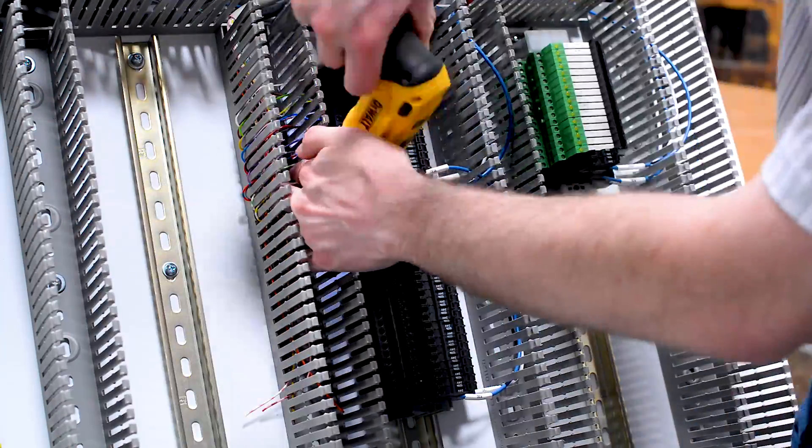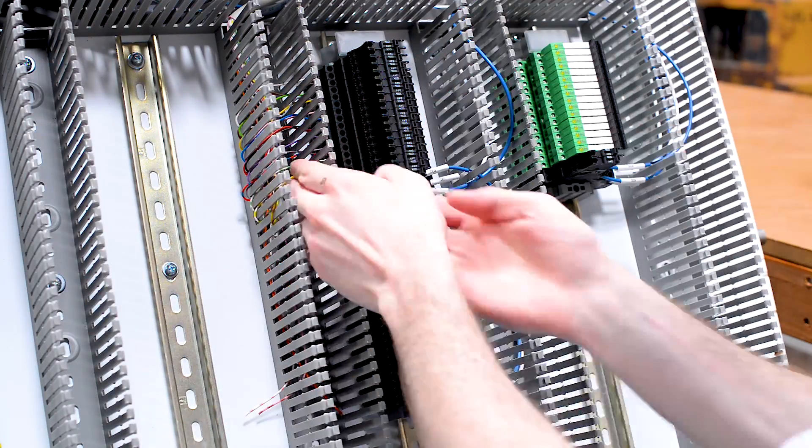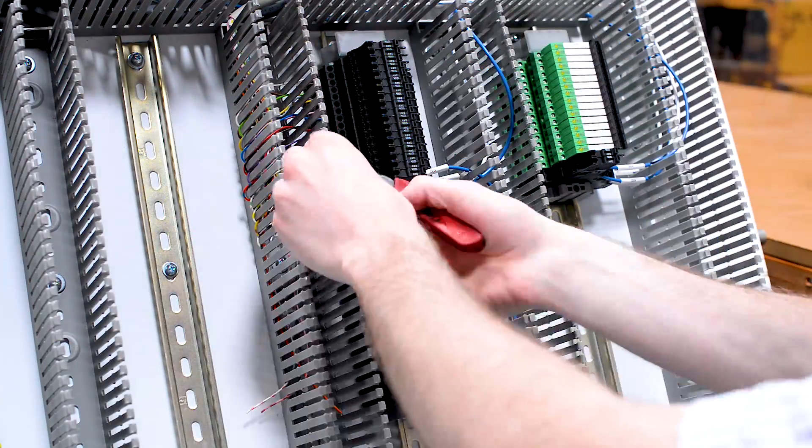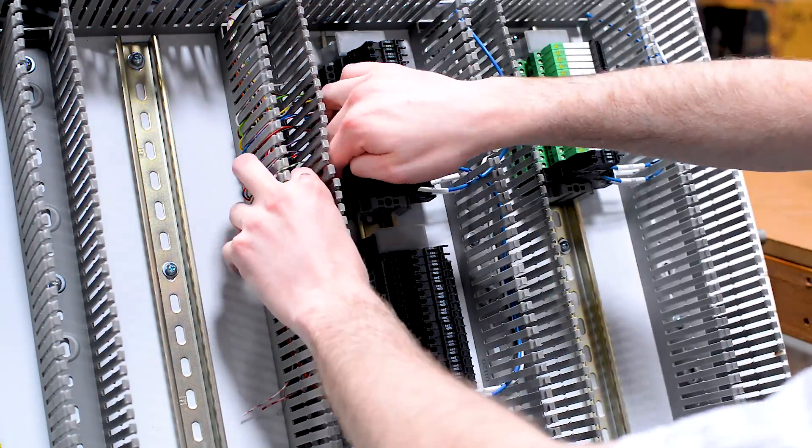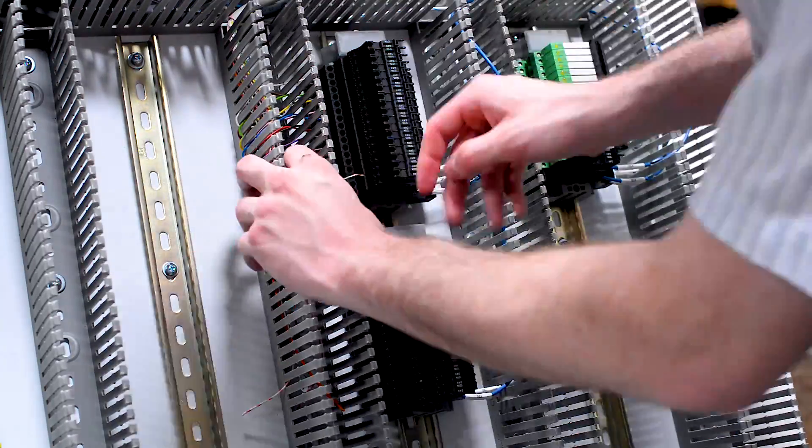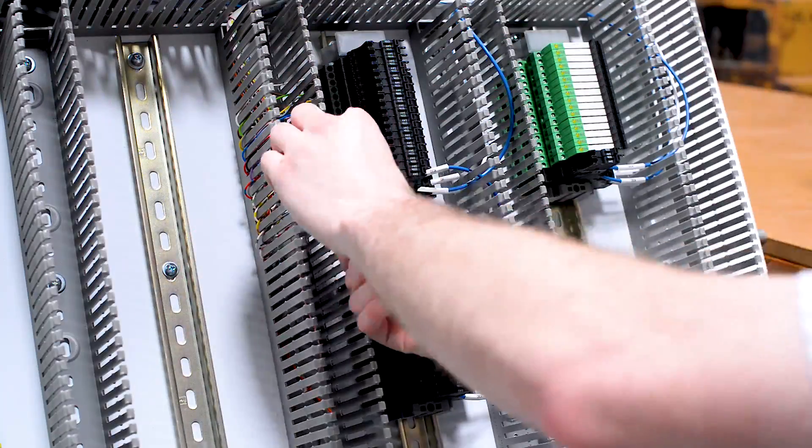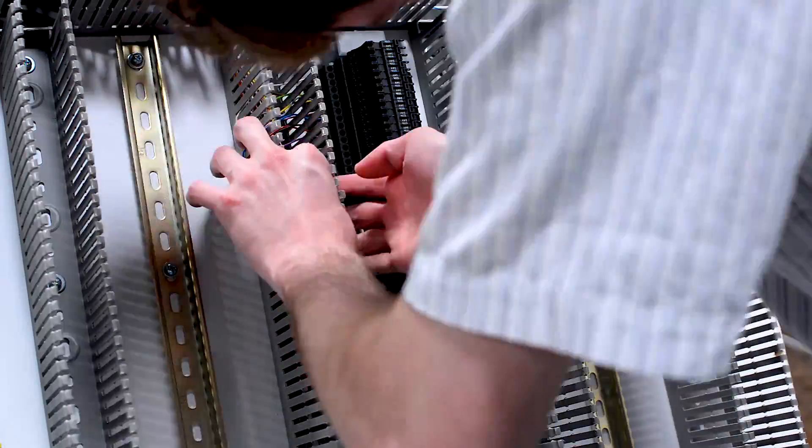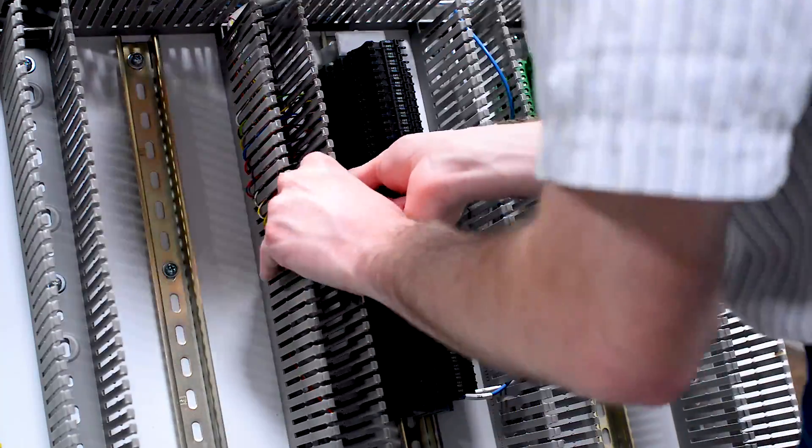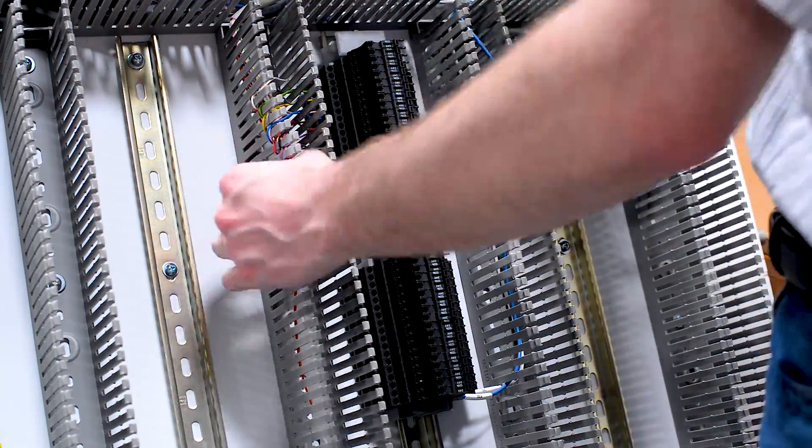It's also important to make sure that we're reading the PLC manual, the hardware manual, so that we can very clearly understand how to wire these digital circuits. Each PLC functions a little bit differently, so they're not all wired the same. So we want to make sure that we understand how the circuit should be wired so that we can make sure that we're wiring a proper loop. We need to make sure that we're putting our power where it needs to go and that we're putting neutral or DC negative where it needs to go so that we ensure that we have a proper loop so that our signals can function and get back to our PLC as expected.